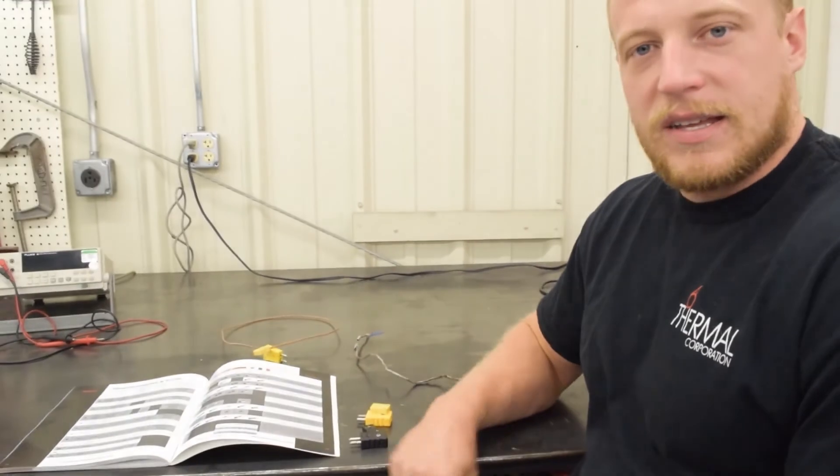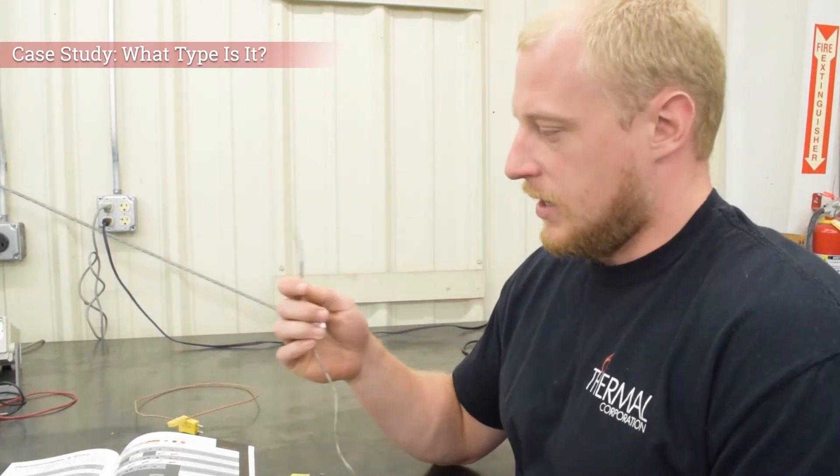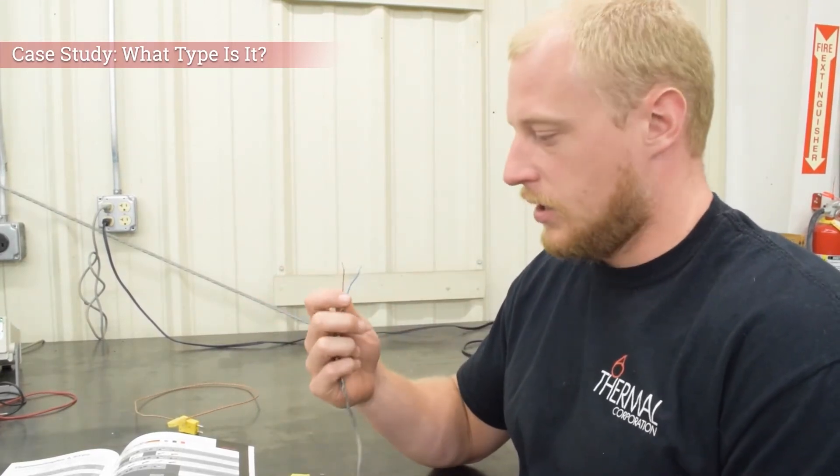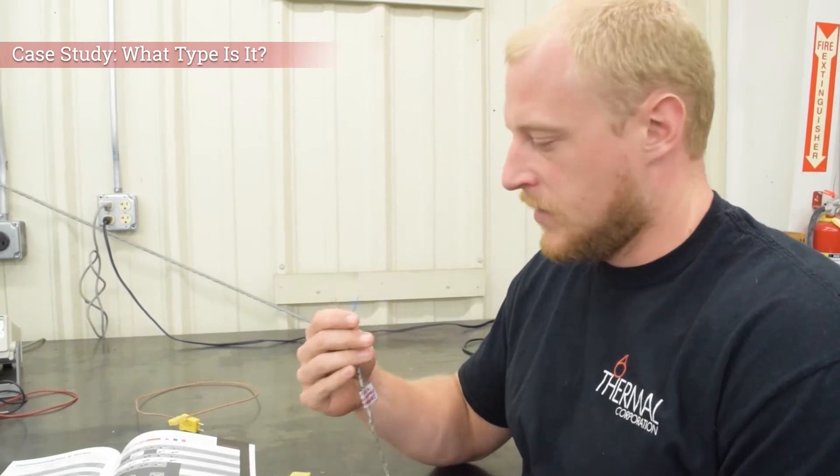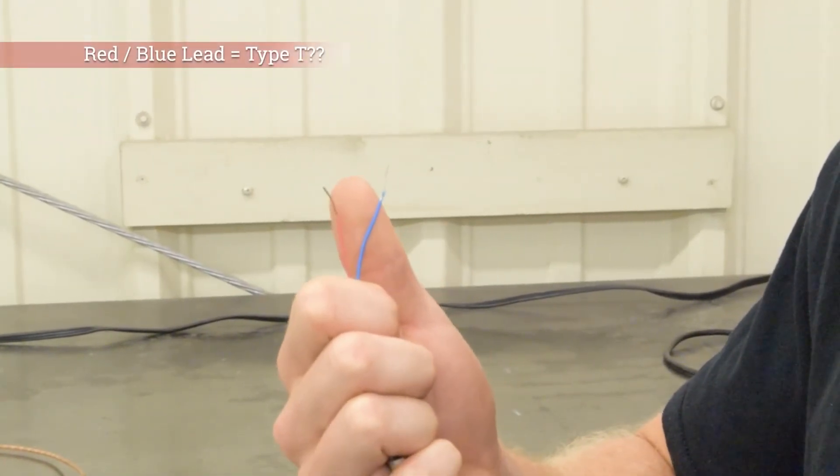Now let's look at a case study of a thermocouple that I brought back from a customer's plant a couple weeks ago. They had this thermocouple and it was no good and they didn't know what type it was. So when you look at it, it's got a red and blue lead which would seem to indicate type T from our discussion that we just had.